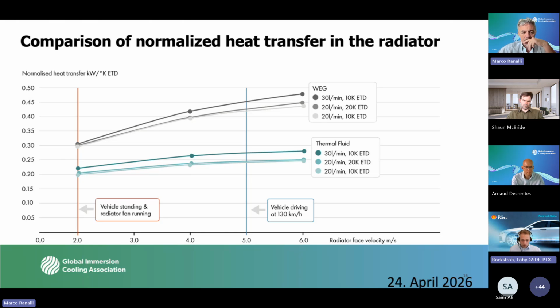Our thermal fluid has a lower heat capacity rate and a lower heat transfer coefficient. However, if you look at the overall system, the keen-eyed will see the normalized heat transfer given here in kilowatt per Kelvin effective temperature difference—that's the temperature difference between the air and the working fluid, being water ethylene glycol or thermal fluid.